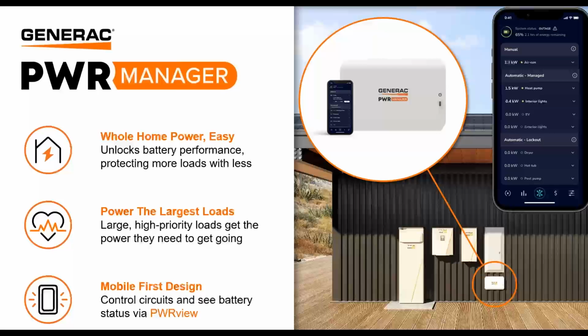Yes, homeowners have the ability to turn loads on and off from the mobile app, and the Power Manager's app interface is built right into PowerView, which is already the homeowner's app for PowerCell. But if everything's programmed well from the install, it should be a hands-off experience for the homeowner. We'll turn the well pump off if it's pulling too much power, and then turn it back on when that power is available. The way this works is you basically assign up to 6 loads in priority from 1 to 6.